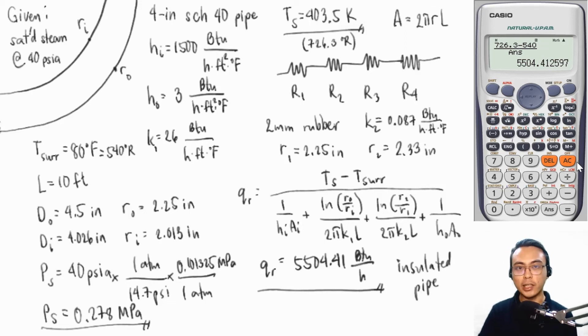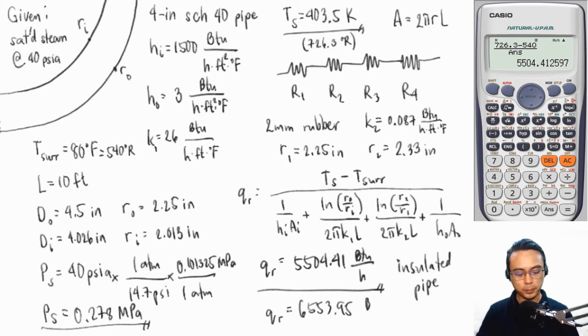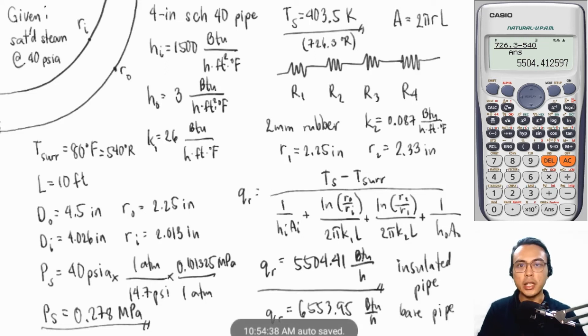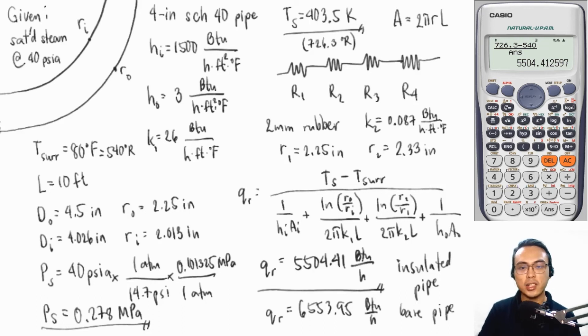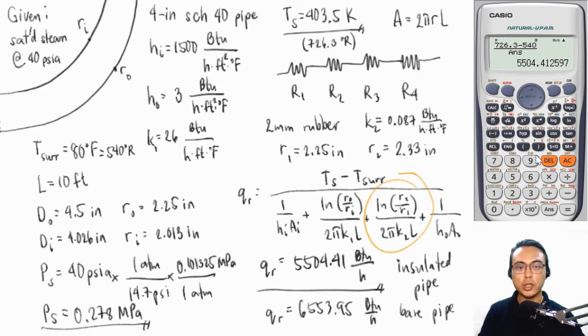Comparing the insulated pipe to the bare pipe, we had earlier determined 6,553.95 BTU per hour for the bare pipe. We now see the effectiveness of our insulation layer. The thin layer of insulation lowers the rate of heat loss from 6,500 down to 5,500 BTU per hour — that reduction is due to the additional resistance term introduced by the insulation.